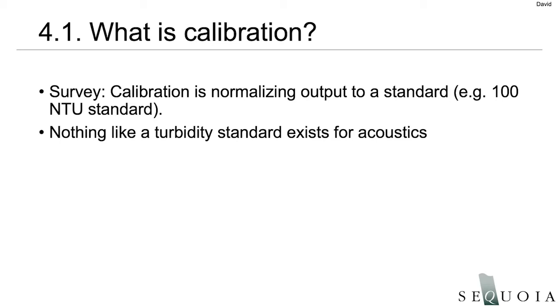You can't go out and buy an NTU standard and use it for acoustics simply because a turbidity standard is very fine particles and it's designed for optics. When you make something like an ABS, you have to come up with your own, essentially. Yes, and certainly turbidity sensors have the advantage that it's not that difficult to make a stable standard. You can make it from very fine particles that don't settle and so on. For people who are accustomed to using turbidity standards, it's a bit of a mental adjustment to have to think about the ABS and how it's sensitive to larger particles.